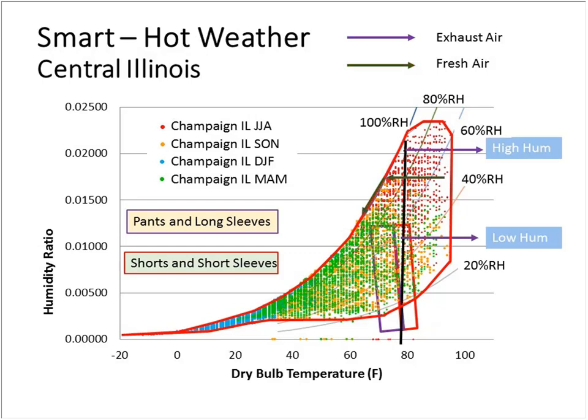And when we look at summer, whether the inside air that we're exhausting is lower in humidity or higher in humidity, because we don't connect up the air from the inside to the air from the outside, as air from the outside is passing through the cooling coils of the heat pump, it can hit saturation, and we condense and dehumidify that air. And the heat from the cooling and from the dehumidification is put in the air that's being exhausted to the outside. And again, you don't see a moisture change in that as we pass to the outside.